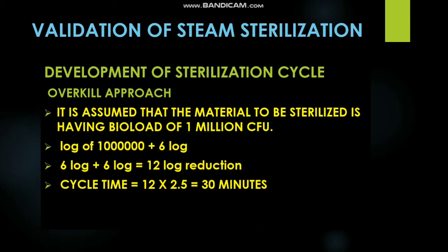So if the overkill approach is utilized, then a 30-minute cycle needs to be done. If the bioburden approach is required, then it depends upon the initial bioload of the article; as per that, the cycles are designed.